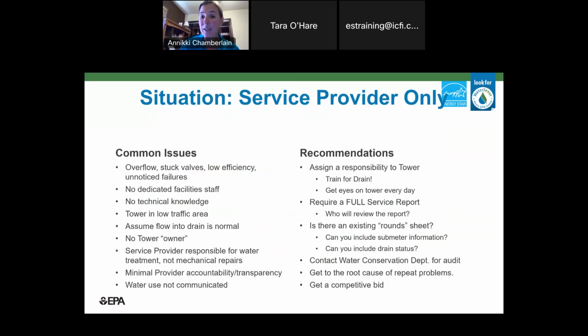So recommendations that we can do. We need to assign a tower. Who is responsible for the tower? Everybody is responsible for something at work, from custodial staff to managers. Everybody has things they're responsible for. So why don't we go ahead and include the cooling tower on one of those? They don't have to be an expert. They don't have to be an operator, but maybe we can just get their eyes on the drain every single day and let them know which drain is good, which drain is bad, or which pipe flow is okay, which one's not. Or, you know what, I get my eyes on it, the blowdown's running.